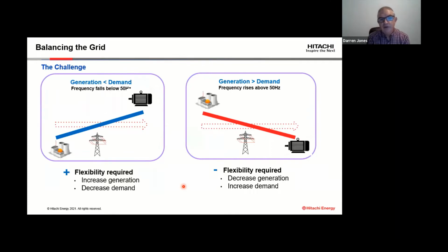And again, the converse is true. If there isn't sufficient demand to meet the generation that's available, that causes frequency to rise, and the action needed is either to decrease generation or increase demand. This is real, live, 24/7 network balancing that happens in every control room up and down the UK. Every electricity network control room in the UK has a large clock on the wall with a readout of the 50 hertz frequency, and it's a 24/7 job to maintain that balance between generation and demand, to maintain frequency. One point I did want to bring out on the last slide is that frequency is actually common across the entire network, whereas voltage levels are quite local. So frequency is the way that the network is managed.